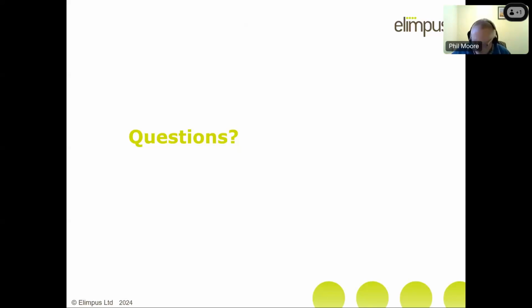Indeed. Thank you, Phil, for a very informative presentation. I have two questions on the screen at the moment. The first one is: if a GIS circuit breaker at 132 kV is not tested to perform reactive switching, we intend to install an additional AIS circuit breaker in series with reactive switching capability. I presume in this case the GIS circuit breaker will still be subject to reactive switching. Is there any solution to counter this situation, please?